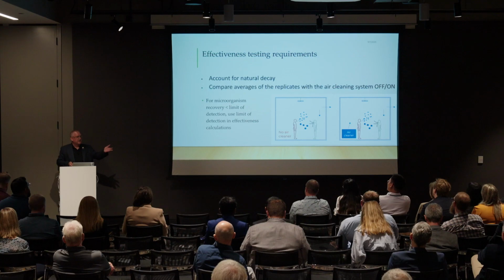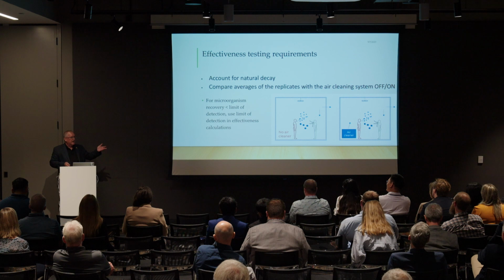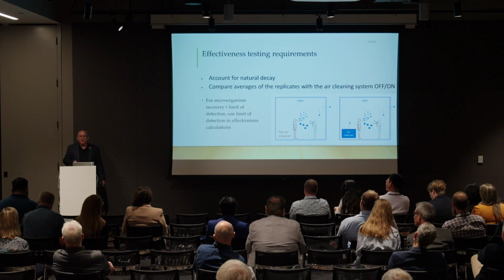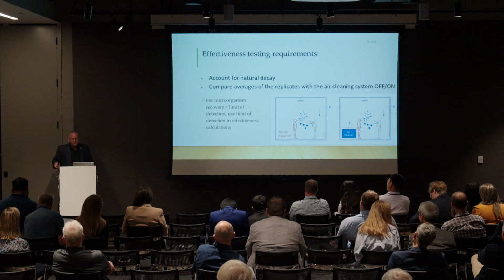I mean, this was one of the problems with manufacturers saying that they had a technology that would remove 99.9% of the active viruses in 3 hours. Well, if you turned it off, you'd probably have lost 85 or 90% in 3 hours because most of the particles would have settled out. And that's why we're focusing on clean air delivery here and not on how long does it take for them to go away, because they will go away.